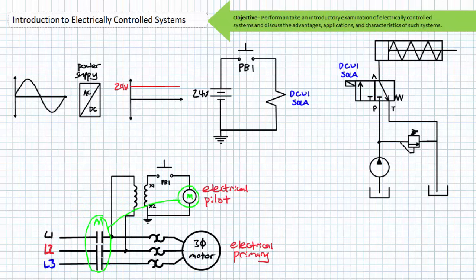In this simple example, there exists a single interaction point between the two aspects of the system, that being the coil on the M contactor. In the electrical pilot schematic, when push button 1 is closed, the M coil would be energized. On the primary schematic, the energized M coil would switch the normally open contacts to their opposite or closed state, and the motor would start.